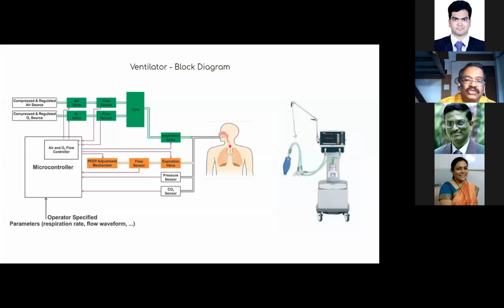When the time for pushing is over, you have to give the patient time to relax. That is when this valve will close and this valve will open. The expiration valve will open. Again, the machine will confirm by the flow sensor that the air is going out.